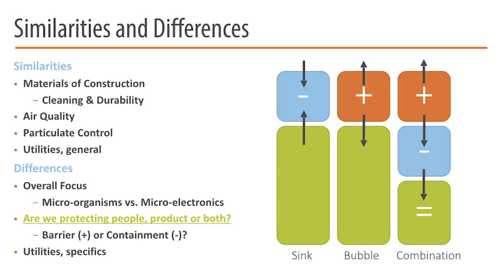Some differences: what's the overall focus of the facility? Is it to protect people, or to protect the electronics? Are we dealing with microorganisms or particulates? So are we protecting the people, the product, or both? That's something we address during the programming stage - the certainty of outcome. How do you want this facility to operate, in its greatest sense? Is it people or product, a barrier or a containment facility? That has to do with the pressurizations.